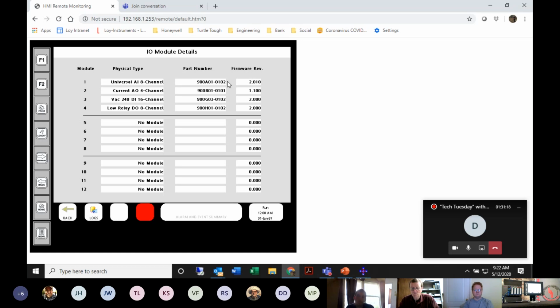So you can put that into the process, then clamp the wiring terminal back down to the front of that card, and you never have to remove any of the wiring. The wiring is still in place, and it's very, very quick.